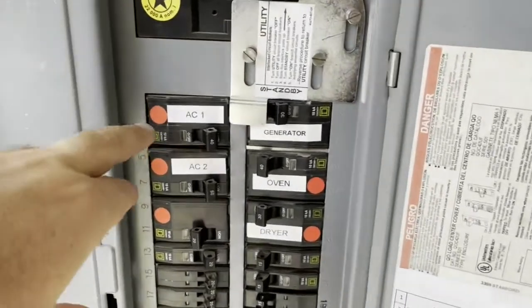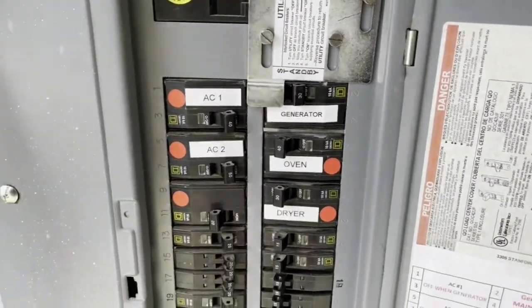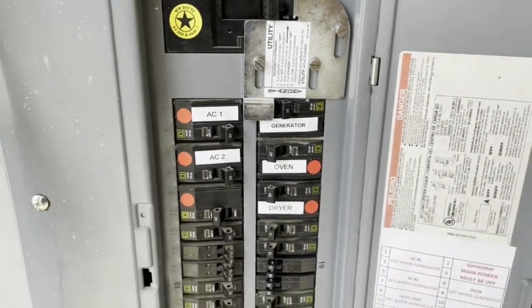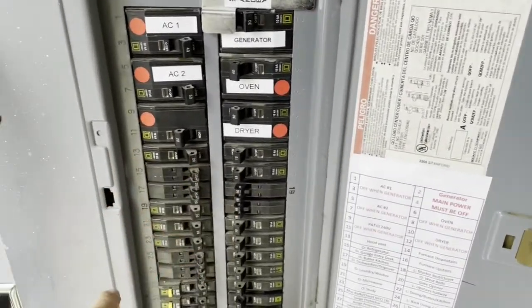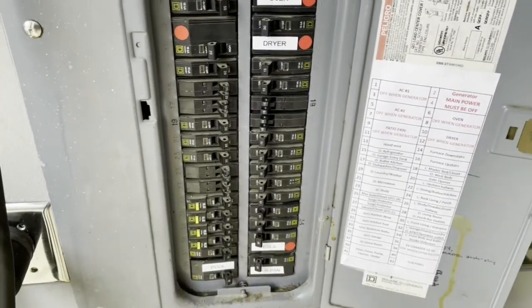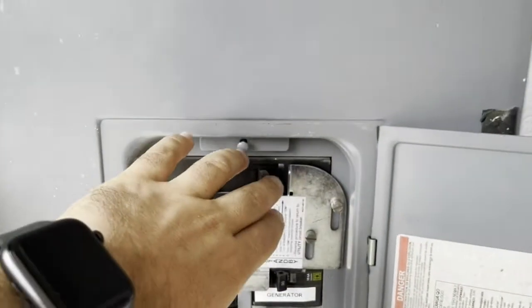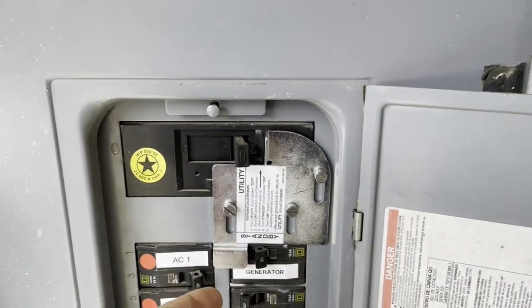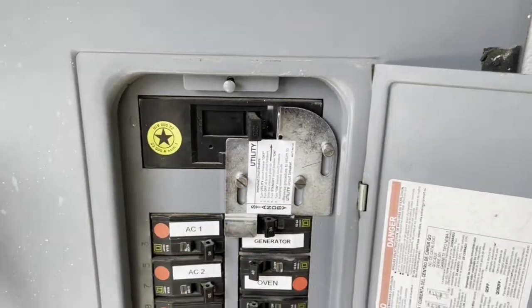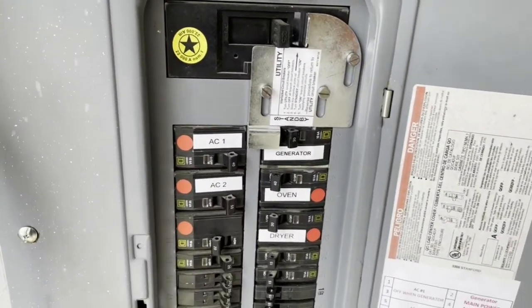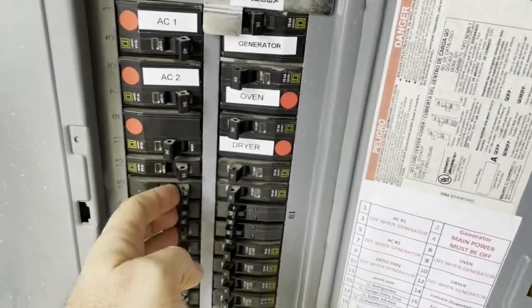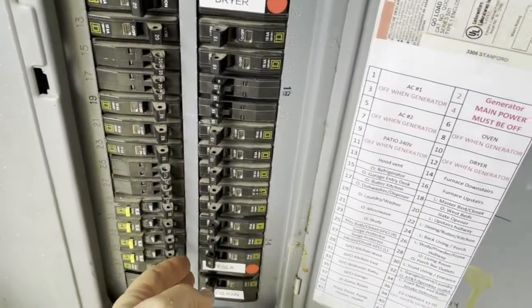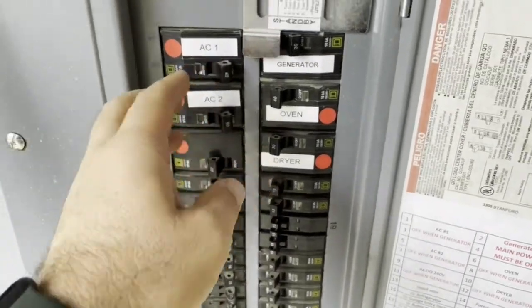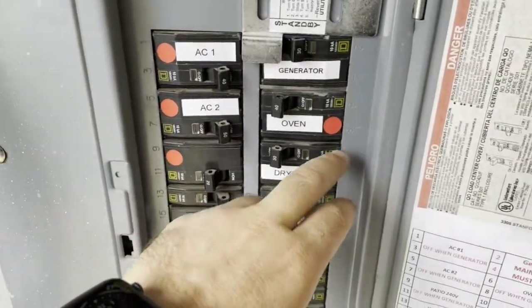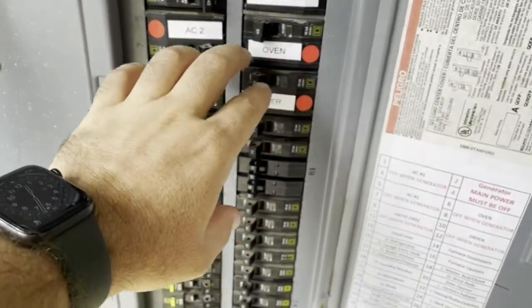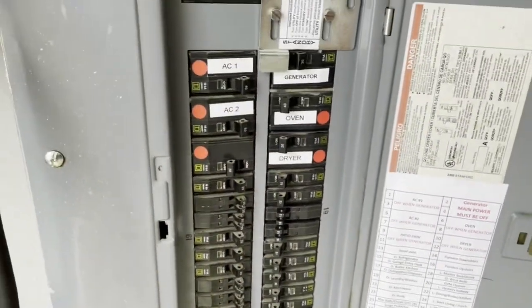I put these red labels here so that once you want to start your generator, the procedure is that you flip off all these circuit breakers so there's no load at all. Then you flip off the main, you flip on your generator, you run your generator and plug it in. Then you start turning on the circuits one by one. And then these red stickers are for the circuits which would never be turned on while the generator is running.